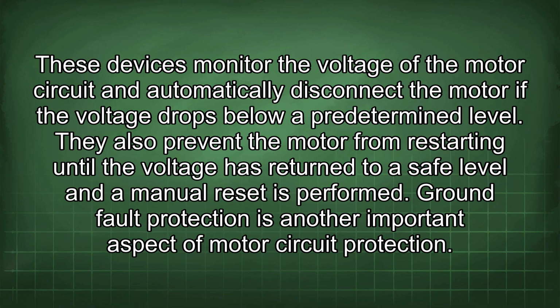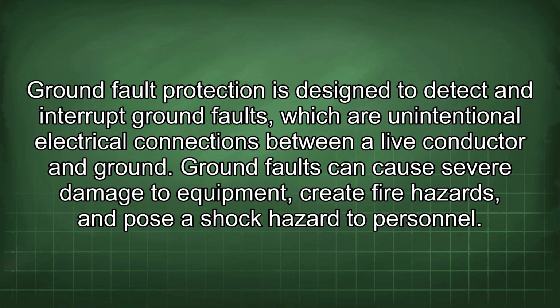Ground fault protection is another important aspect of motor circuit protection. Ground fault protection is designed to detect and interrupt ground faults, which are unintentional electrical connections between a live conductor and ground. Ground faults can cause severe damage to equipment, create fire hazards, and pose a shock hazard to personnel.